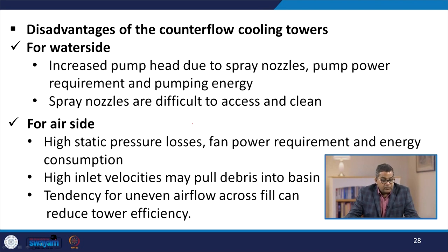Now, if we take the water side first, then there is increased pump head due to the spray nozzle, which raises the pump power requirement and pumping energy. These spray nozzles are difficult to access and clean, and sometimes they may clog over a period of time, and thereby the efficiency of the cooling tower may be reduced.